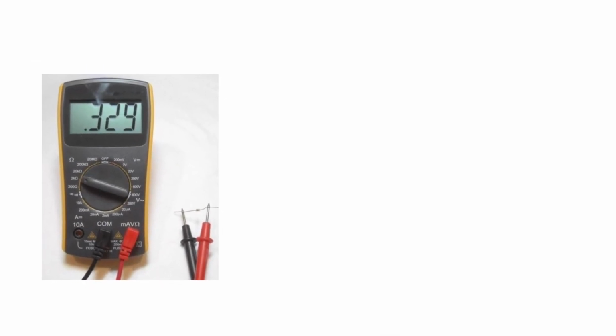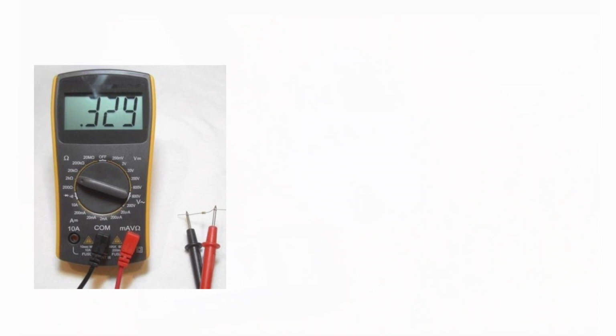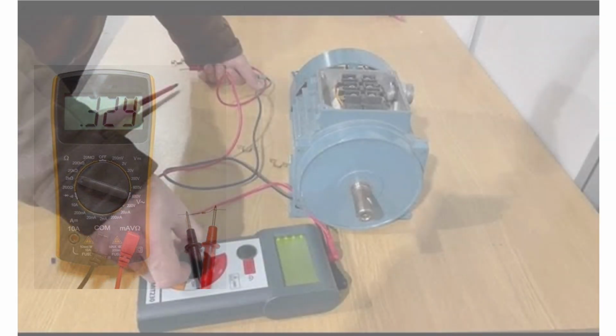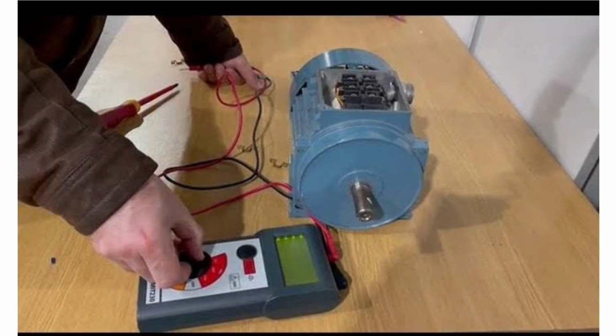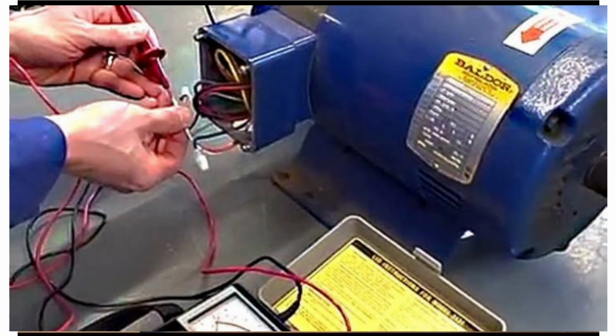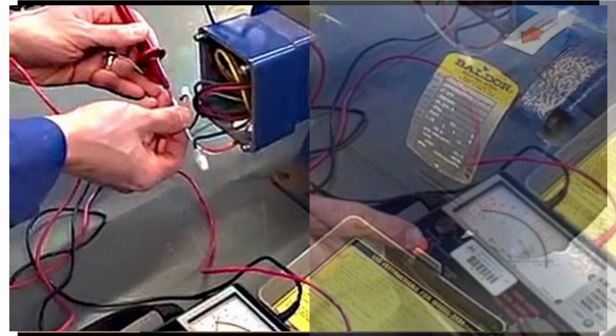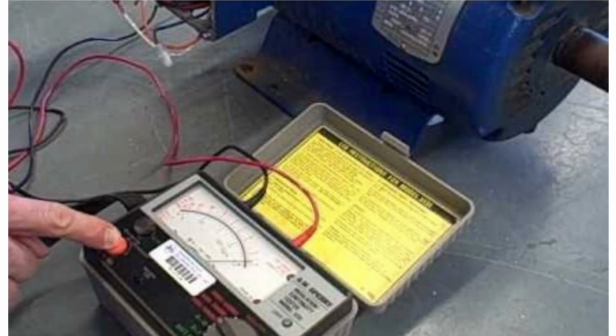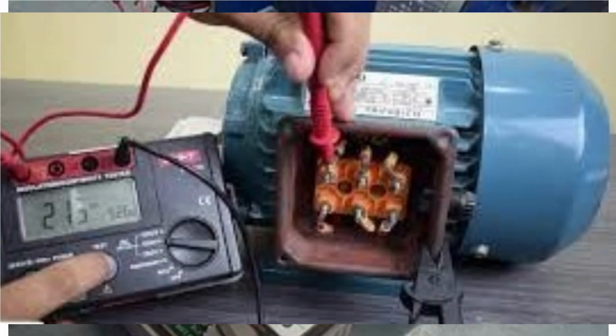Use a standard multimeter to test interphase resistance on all three phases. 1. All readings should be approximately the same and will vary depending on the size and type of the motor. 2. If a dead short, 0 ohms, or overload is detected with the meter, the motor may be bad.